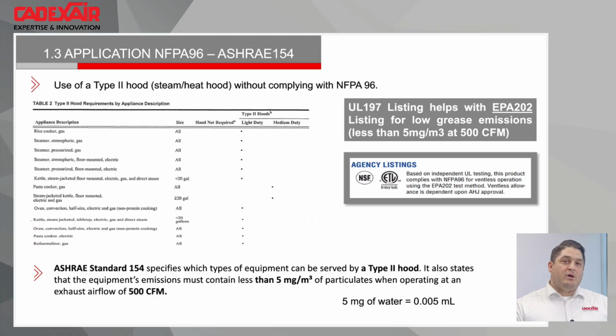So now there's a lot of equipment that has this kind of test. And if you look in the spec sheet, it will be at the top of the page because they pay a lot of money to be there. To give you an example, a lot of Canadians are on the road, so Tim Hortons is coast to coast, so everybody can have a fried potato or something like that from Tim Hortons, and they don't have any commercial cooking hood. It's because they use listed cooking equipment with a catalytic converter, so they're listed to have less than 5 milligrams of grease per cubic meter at 500 CFM, so they can use a normal kitchen exhaust hood, a Type 2 kitchen exhaust hood system.